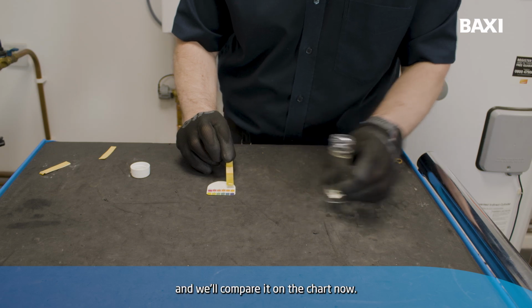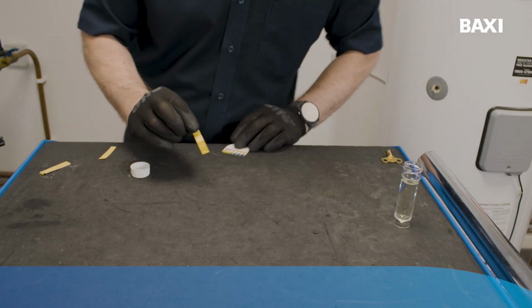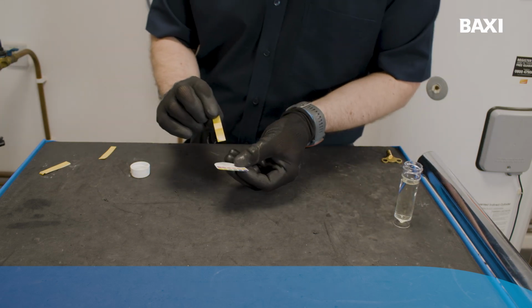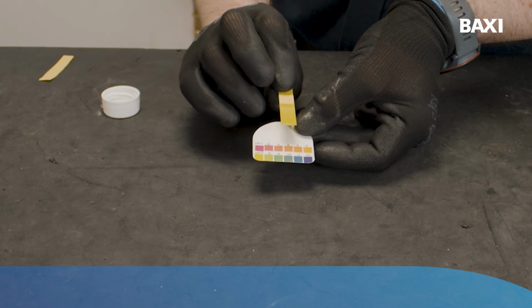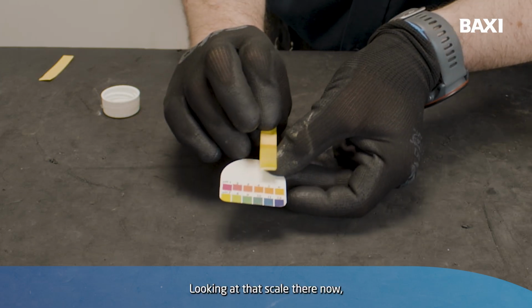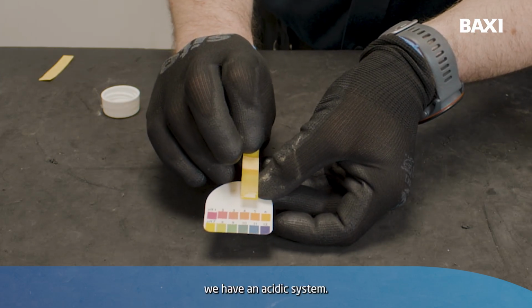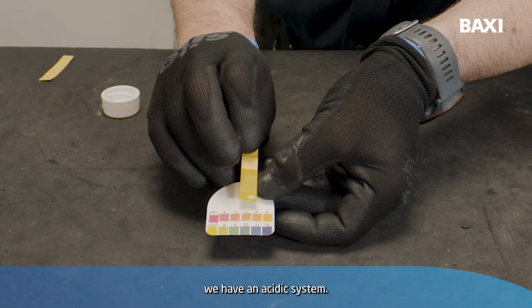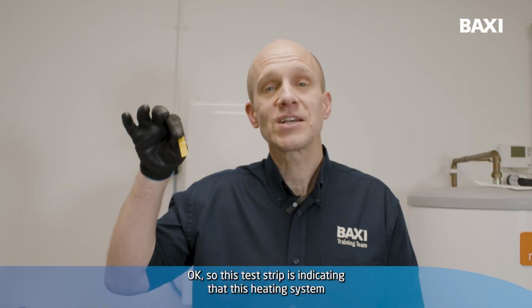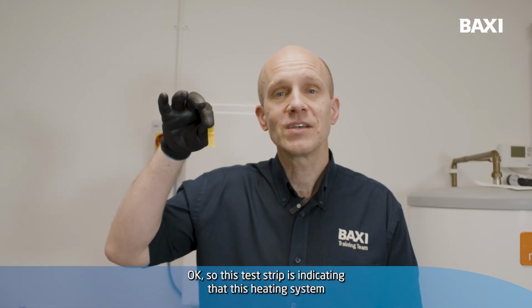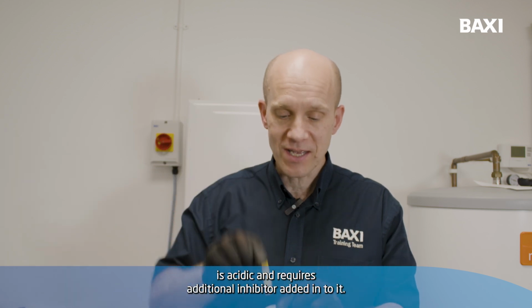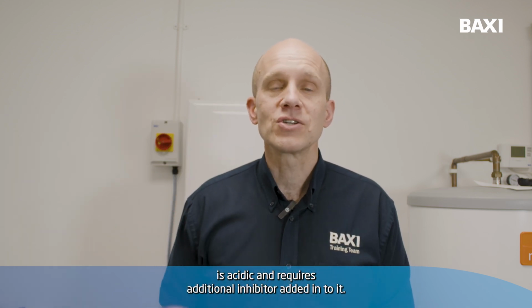We'll compare it on the chart now. Now looking at that scale there, we have an acidic system. So this test strip is indicating that this heating system is acidic and requires additional inhibitor added to it.